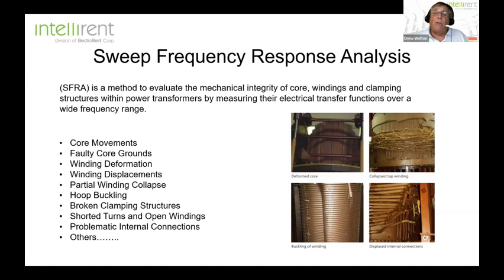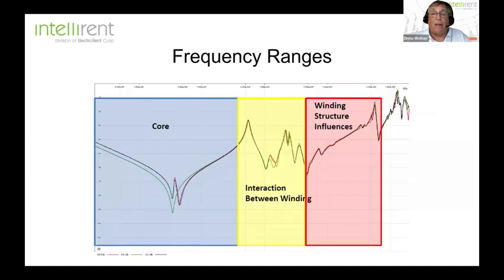Now, what does sweep frequency response analysis look for? Well, it looks for core movements, faulty core grounds, winding deformation, displacements, all sorts of physical, mechanical issues that you have within the transformer itself. And you can see some examples of this on the side. Well, one of the things that we know when you do an SFRA test is, depending on where you see the abnormalities, it can kind of pinpoint exactly where that might be. In the lower range, it could indicate a problem in the core. In the middle range, it's the interaction between the windings, and then the winding structure influences your higher range.